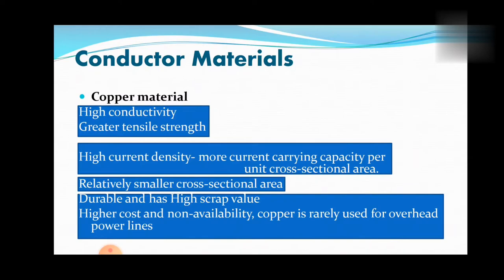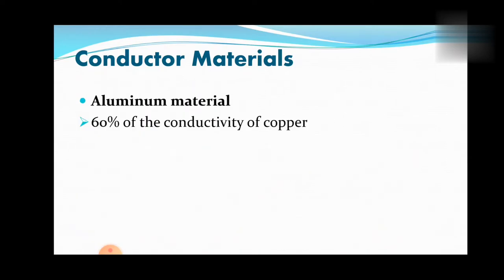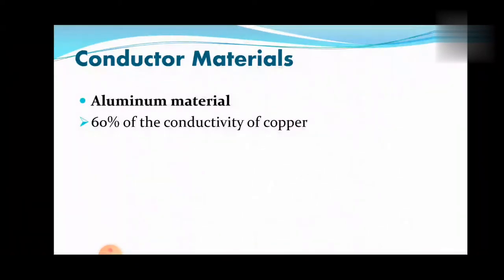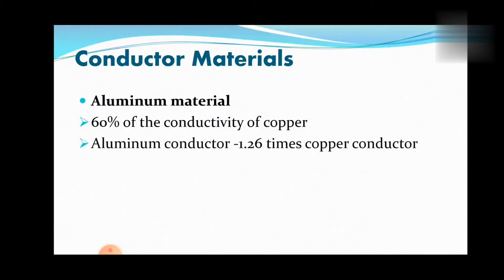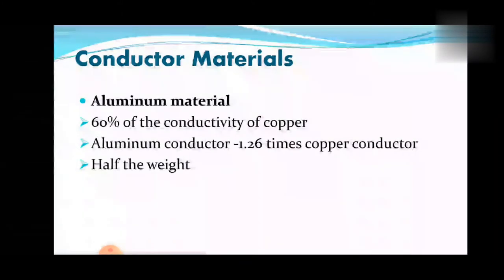Regarding the aluminum material, aluminum has about 60% of the conductivity of copper. That means, for the same resistance, the diameter of an aluminum conductor is about 1.26 times that of a copper conductor. However, an aluminum conductor has almost half of the weight of an equivalent copper conductor.